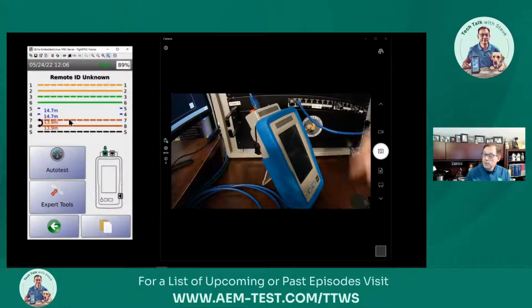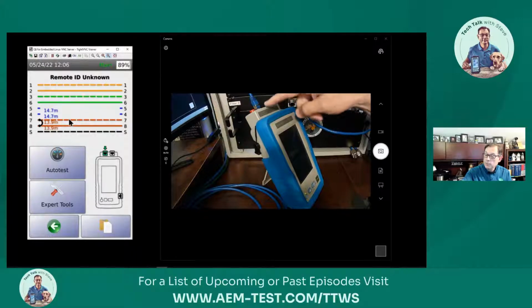That tells me, here's the cord coming from my test head—this issue is going to be at the other end of that link. If it was right here, it would show more like 2 meters. So we know it's at the other end, and I immediately know which jack is going to be the suspect. Where's my problem going to be? I'll take care of that.